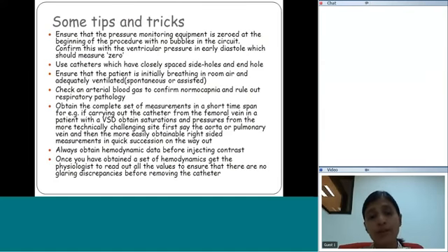I have found sometimes that the end-hole catheter gets too wedged. Tissue gets into the single hole in the catheter and makes it difficult to get measurements. So if you're having such problems, then maybe you should use an end hole plus closely spaced side holes type catheter, so that you don't have this issue of over wedging and damping of the trace.